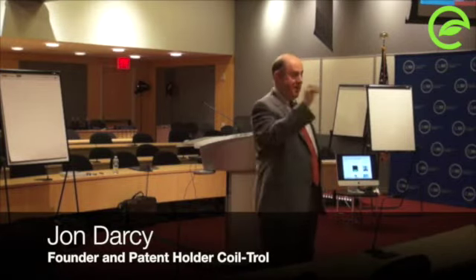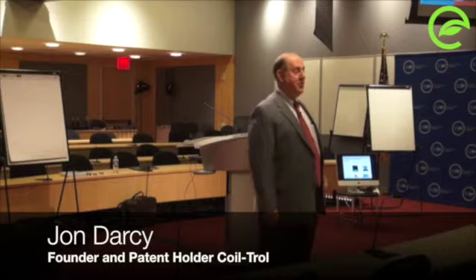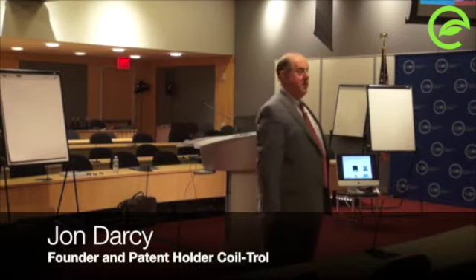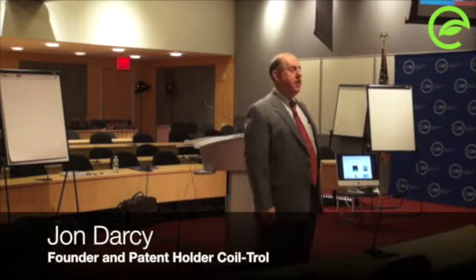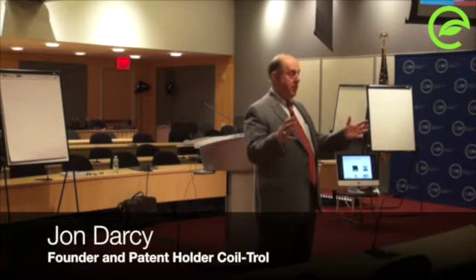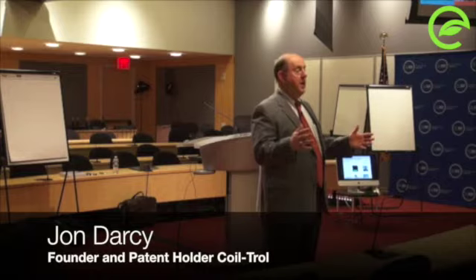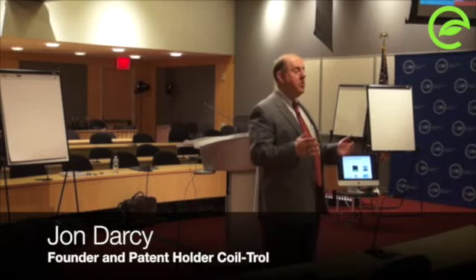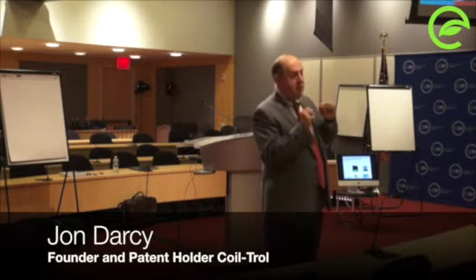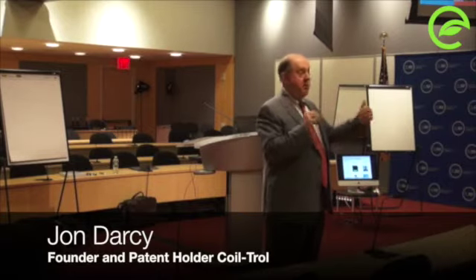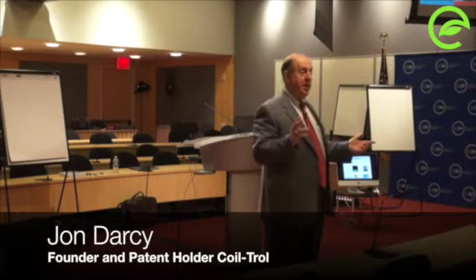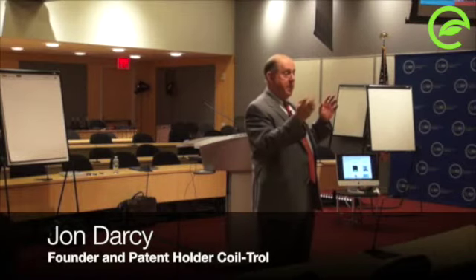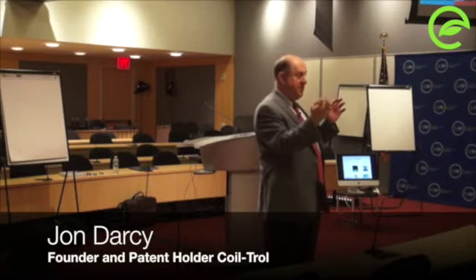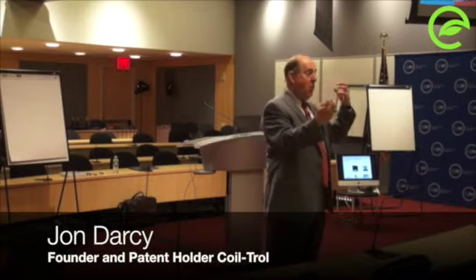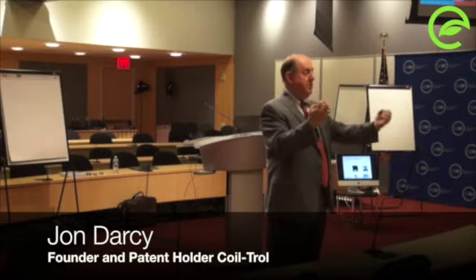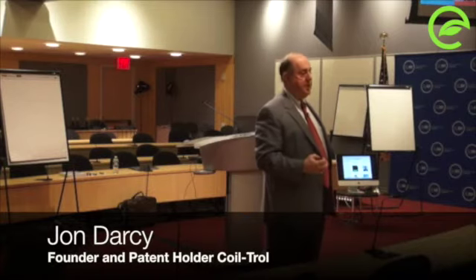Your damper opens up and is discharging air out the side of the building. The humidity is coming upstream from that flow. The pressure is not high enough to overcome the delta pressure of the vapor pressure. It means that when your dampers open up, say you open your damper 10% or 5%, the humidity comes through there at the speed of sound. If the vapor pressure in the building is a lot lower than the vapor pressure outside, the vapor from outside is going to come into that building at the speed of sound.